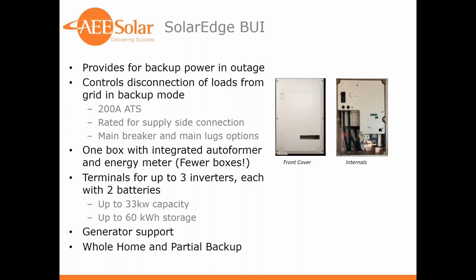There are terminals for up to 3 inverters, each capable of powering up to 2 batteries. So from this one 200 amp device, you're able to pair up to 33 kW of inverter capacity and up to 60 kilowatt hours of storage. That's with the current storage option of LG Chem RESU 10H. We've long been awaiting a SolarEdge branded battery that promises to deliver even more power for these systems. Also included, we've got a path for generator support, and again, this device now facilitates whole home and partial home backup. Whole home being the nirvana that we're all looking for, that helps us get around those choices of what can I afford to back up and what can I afford not to back up.